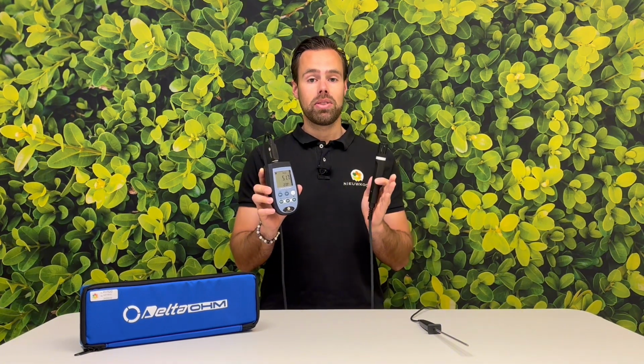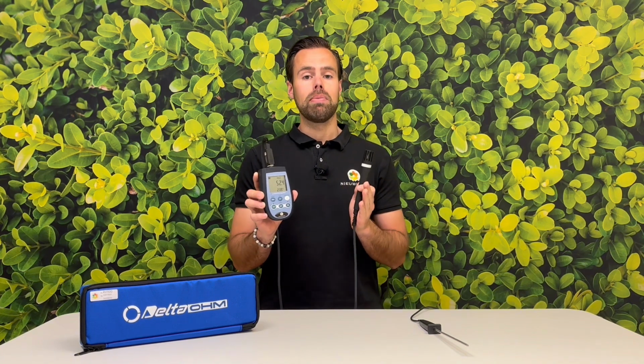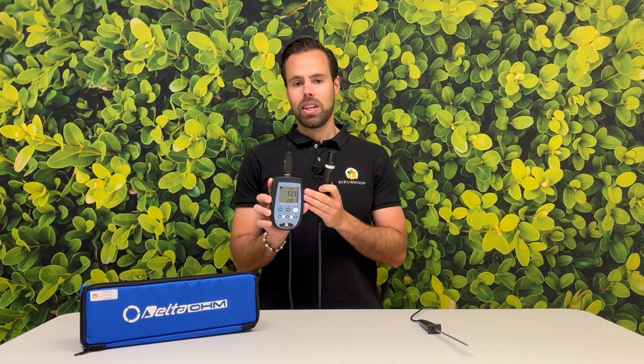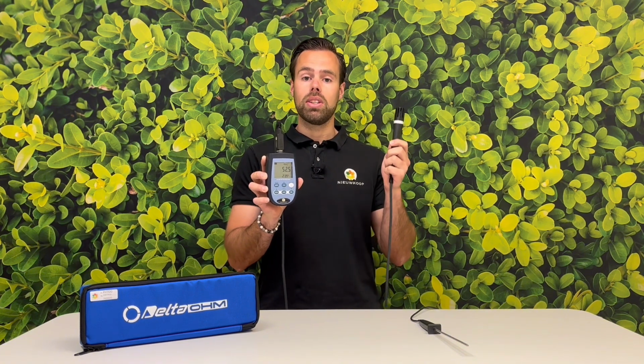Another two cool features of this machine are the min-max measurement and the relative measurement. The min-max measurement basically means that it automatically saves the lowest and highest value measured. Then the relative measurement. It measures the difference between the starting point and the moment that you are measuring.